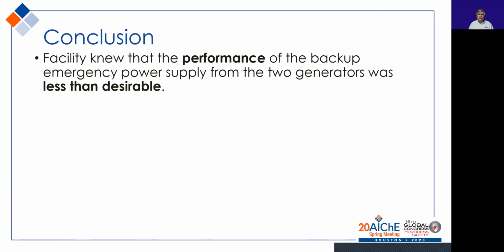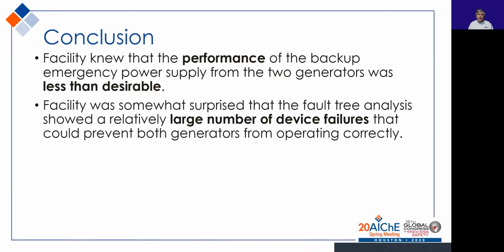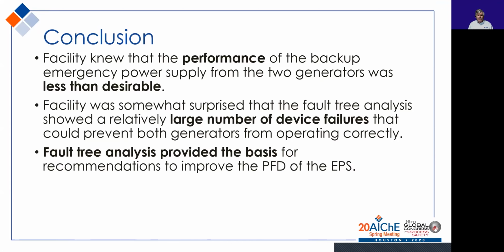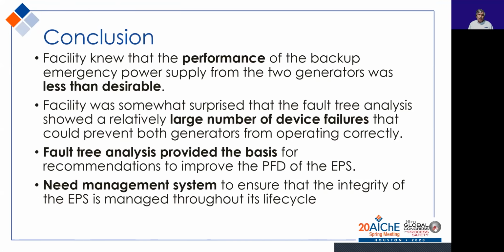In conclusion, the facility knew that the performance of the backup emergency generators was less than desirable. They were surprised that the fault tree analysis showed a relatively large number of device failures that could trip both generators. The fault tree analysis provided the basis for the recommendations, and we realized we needed a management system to ensure that the integrity of the EPS is managed throughout its life cycle. This is one example where we have to go beyond LOPA to more details because two redundant devices are not fully independent.